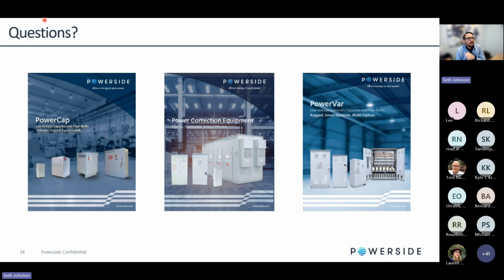The standard is a point of common coupling standard. You can meet that standard, let's say, if you put series connected LCL filters on every single VFD. That is possible, but the standard is not an equipment related standard. And so one of the benefits of doing a centralized correction approach is that you have visibility at the closest point to the point of common coupling to do the harmonics correction. And depending on how we configure the filter, you can get significant benefits downstream as well.